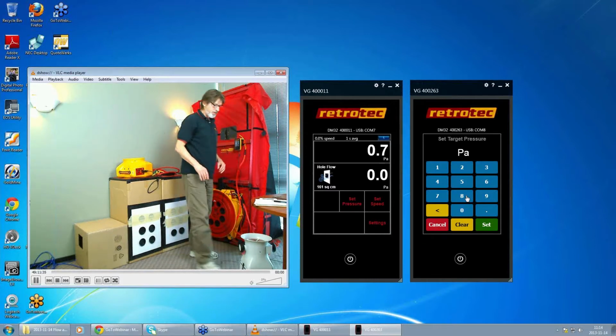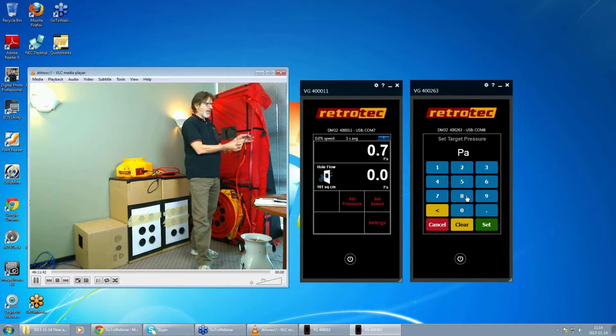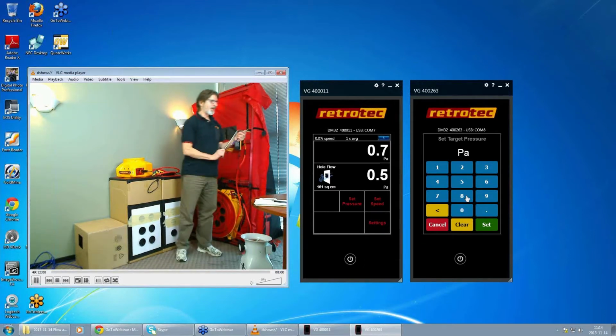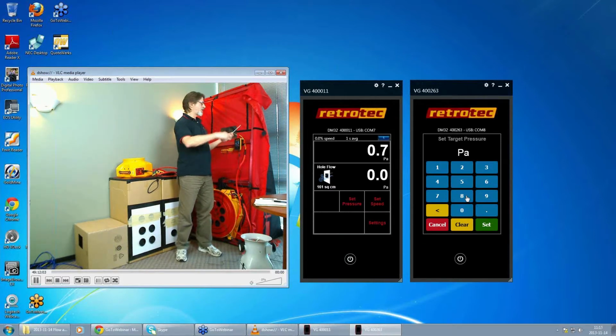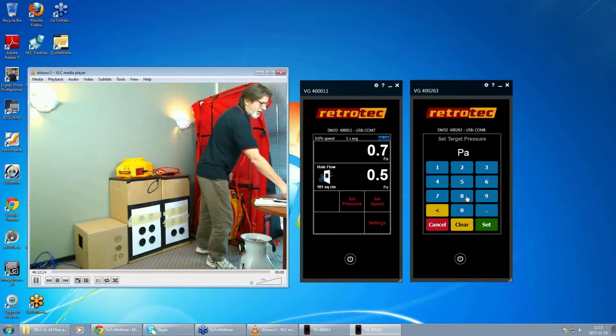Okay, so this is a static pressure probe here, and it has only one connection on it. So it's for measuring static pressure, and it's got 4 holes around the outside here so that no matter which way the air is blowing at it, it's just going to pick up the static pressure, not the background and not the velocity pressure. Now, a pitot tube, by contrast, has got 2 connections, one that goes to this little hole here that's meant to face upstream into the airflow, so it gets the velocity pressure, and then holes around the outside that pick up the static pressure. So this is something you can use to measure velocity. This is something that you use to measure static pressure. It's a common mistake that people seem to get those two things confused.